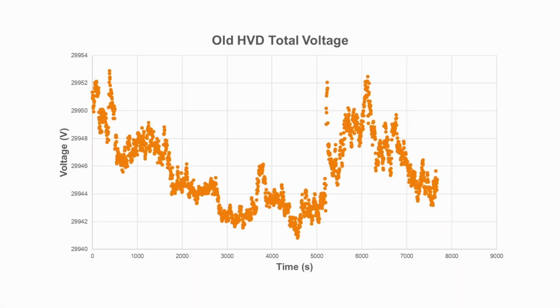Now, we already had a high voltage divider, it just stopped working properly. This is a plot of our old voltage divider, total voltage against time. As you can see, the voltage is not constant, which means we do not have control over the voltage, therefore we do not have control over the beam energy, therefore we cannot produce an accurate laser spectrum. This is a problem. We've run a bunch of diagnostics, it's a dud, we needed a new one.